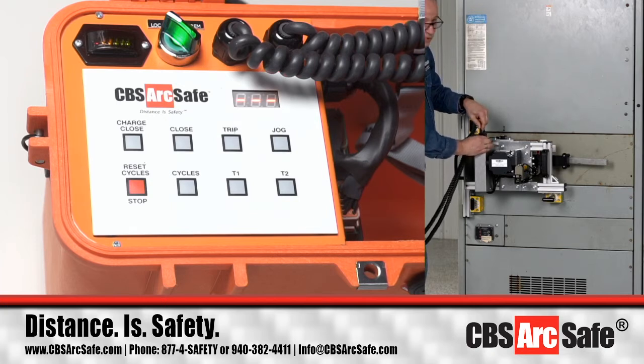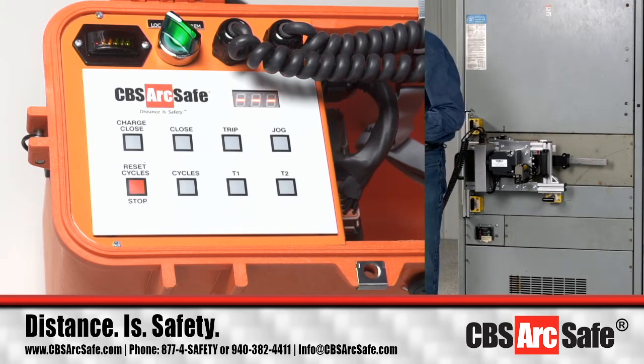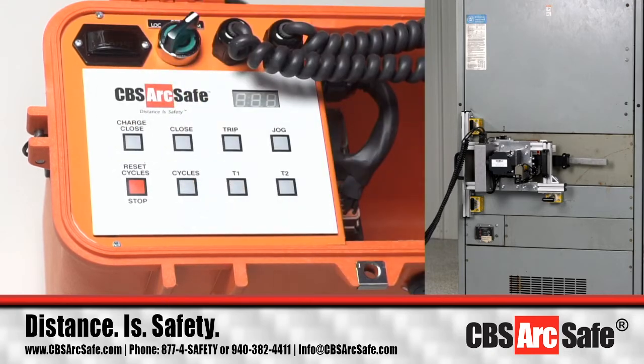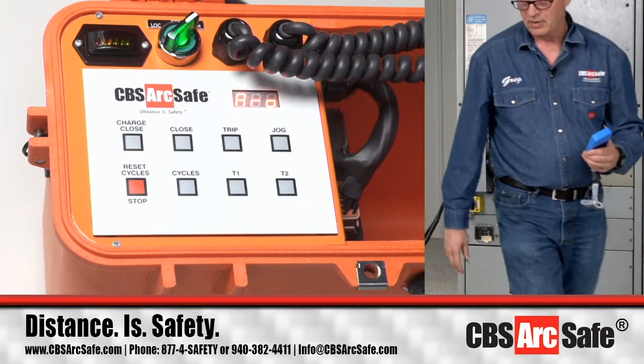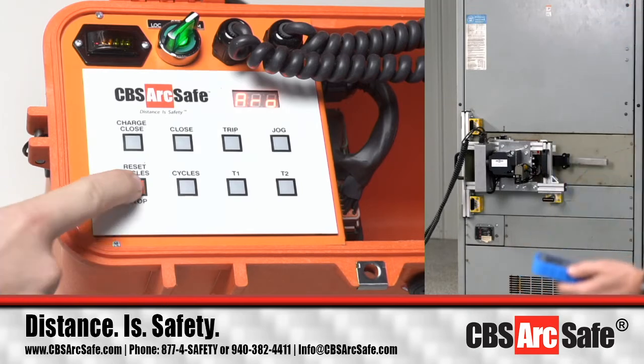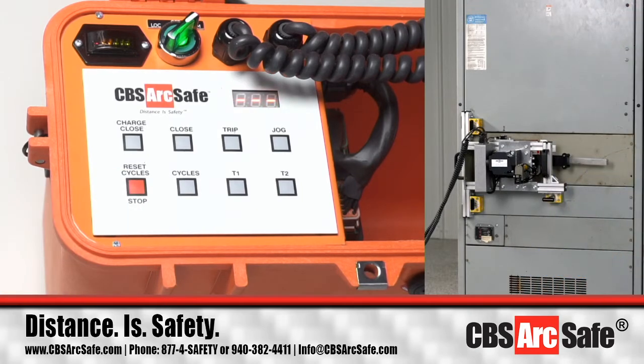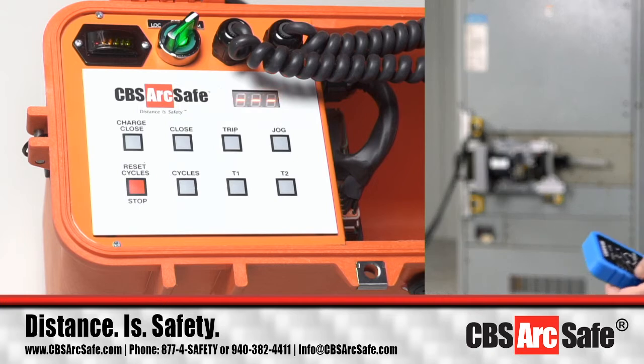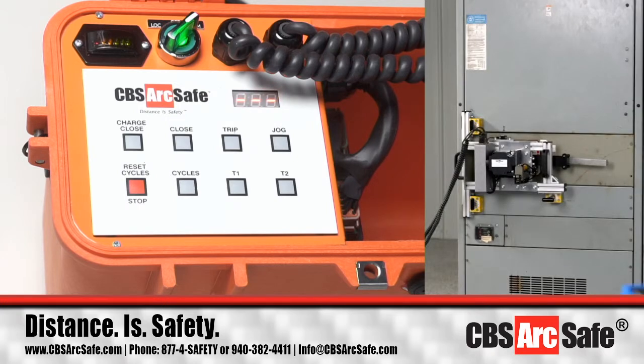Now, for the purpose of the video, I'm just standing right here next to the switch. In reality, if I switch this over to remote now, I'm going to turn it on here, and it says on, and I'm going to step out of view or back up here so that we can do charge close. We only have to push it once, and it's going to cycle up and come down and close it. And then I hit trip once, and you hear it retract the actuator. That's how this is set up to operate.